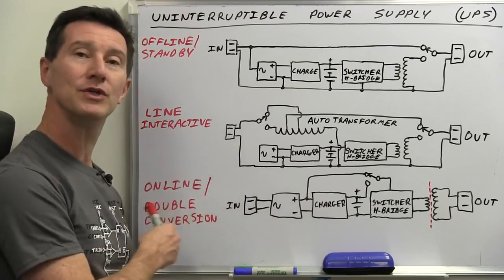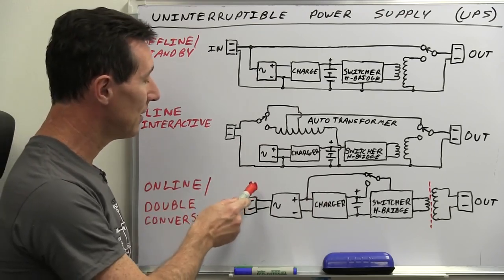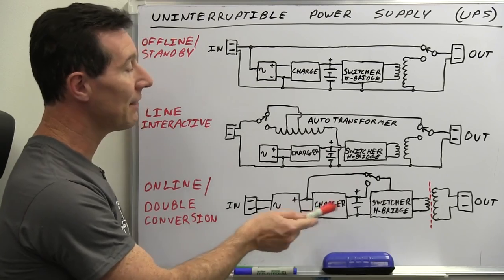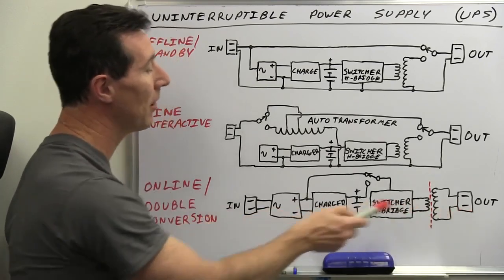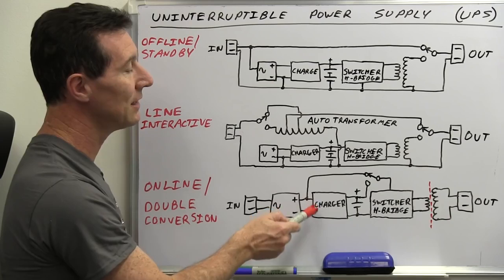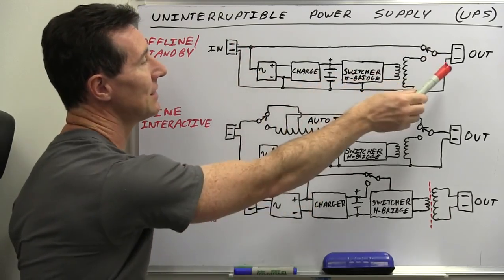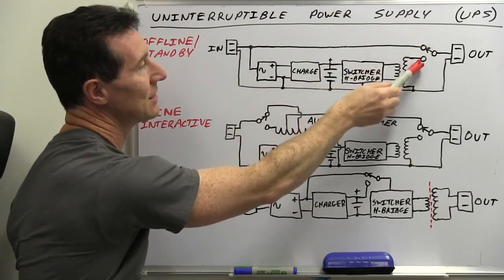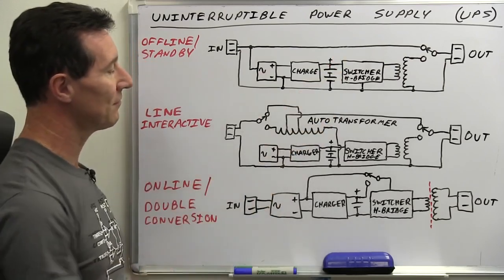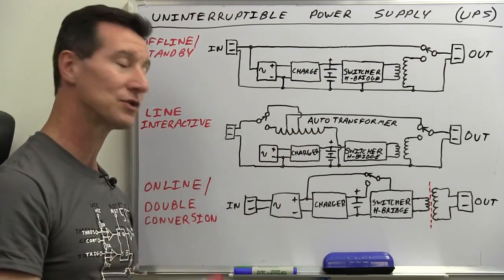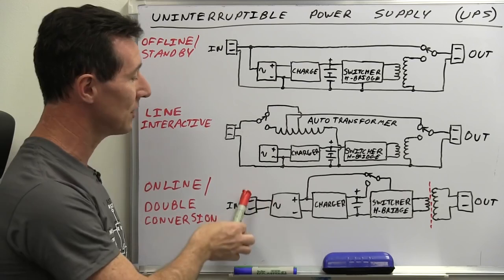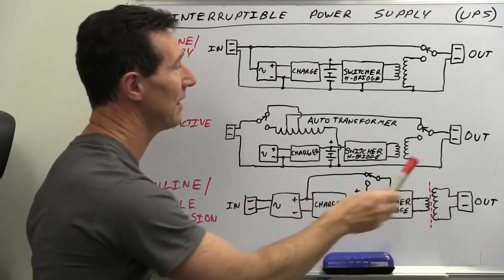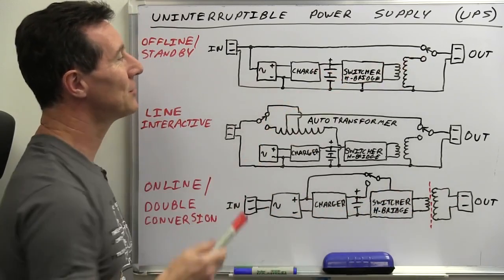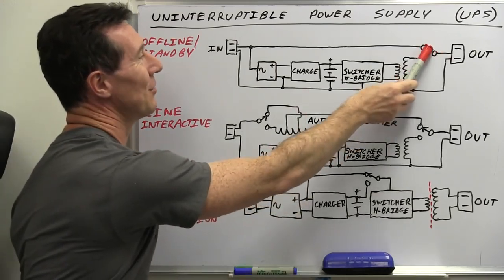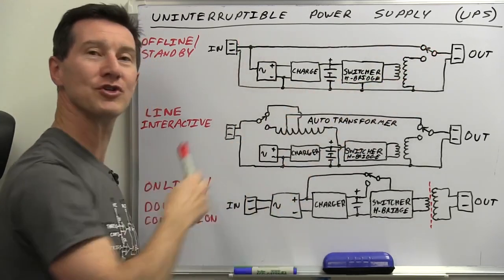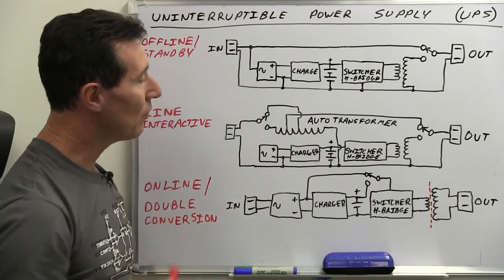And that's why it's called double conversion, because we're converting AC into DC, and then the output here is permanently running from that DC connection. It's not switching between AC and DC sources effectively. It's always powered from that DC source. And that's why they call it double conversion, because you're converting once and then you're converting again. Yes, this one does it up here too, but there is the option to switch through with no conversion at all. Hence the name double conversion.